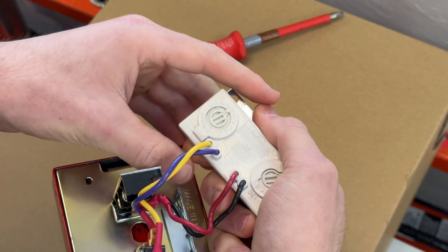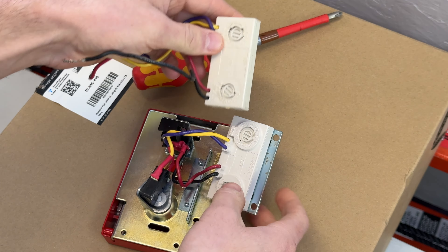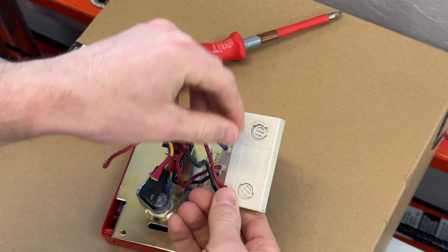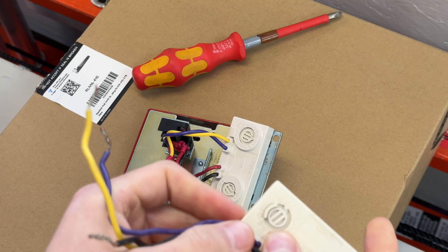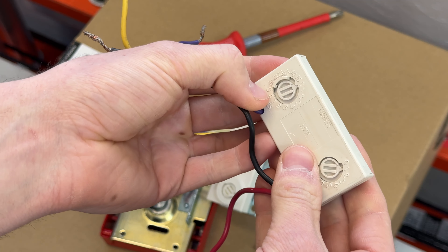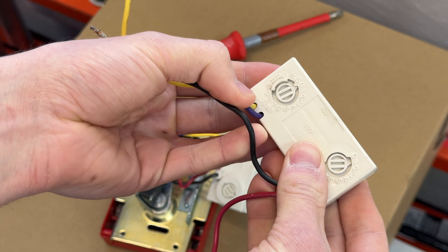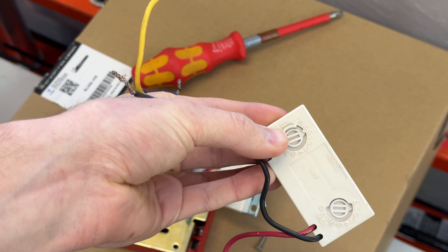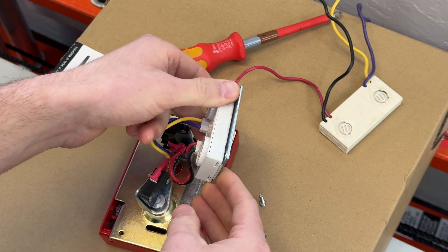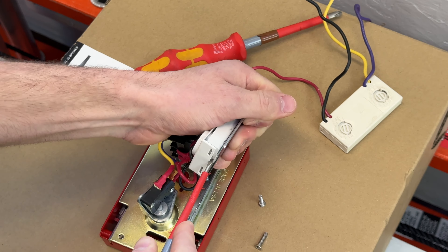This is totally just a normal mini module. I've got another older one to compare — you can see it's the same size. You still have purple and yellow for your conventional side, red and black for your SLC. You'd break it off depending on the panel you're using, because many panels like the AFP-200 can only have 99 detectors — same with the Fire-Lite 9200. You have to break that off to keep going to 159. I'm not sure how they got this attached in here — maybe these little clips.